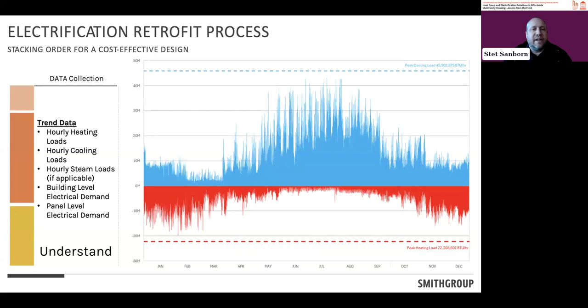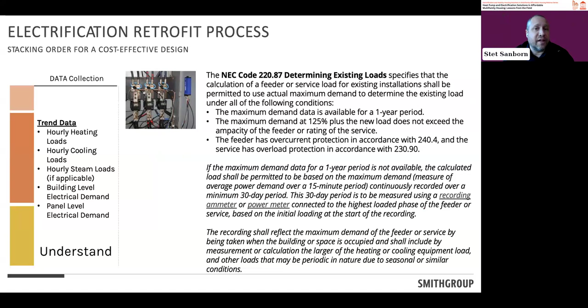But something else to double check is that the electrical code actually allows you to do a panel study as well. So if your engineer comes back and says, oh, there's no capacity in this building because they just looked at your panel, encourage them to go back to NEC code 220.87 and do a panel study. Check to see how much energy you're actually using and how much capacity you have left. It's actually prescribed in the code that you're allowed to overload the panel, provided that you have data showing how the existing usage works. So you might have more capacity than you think in your existing system.